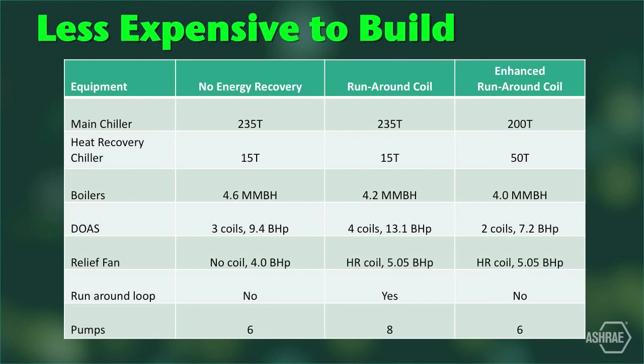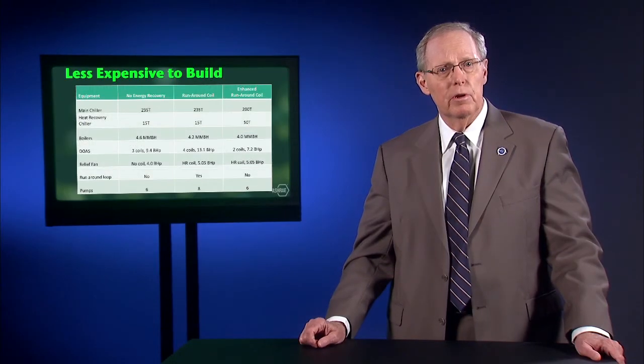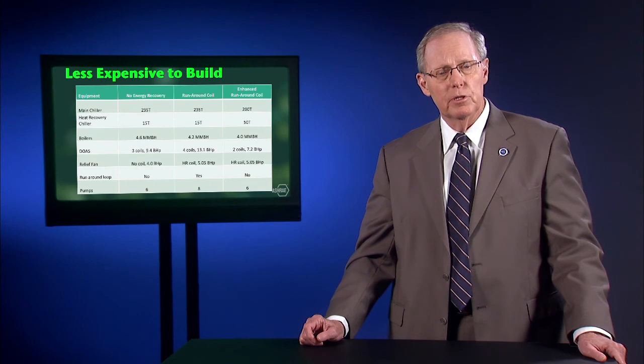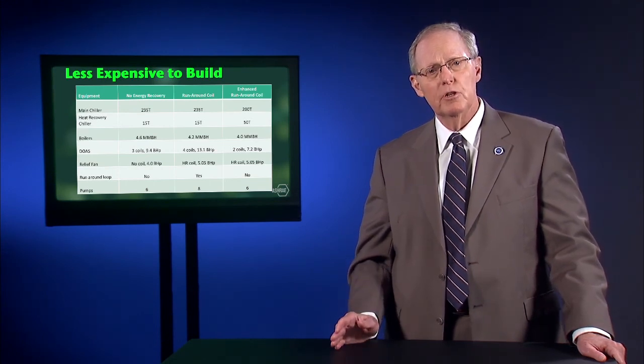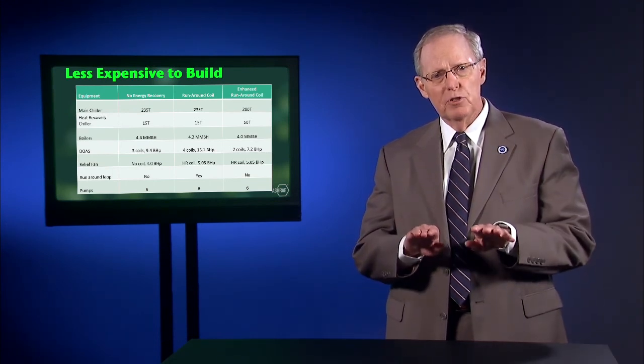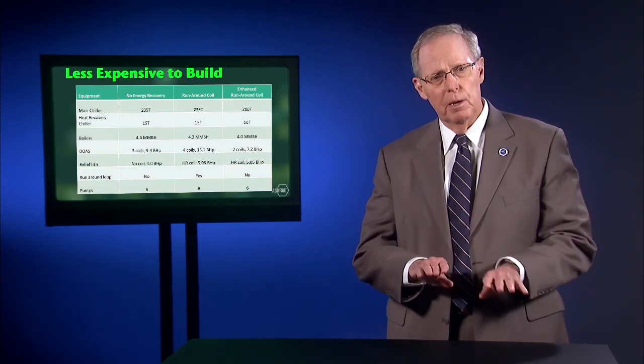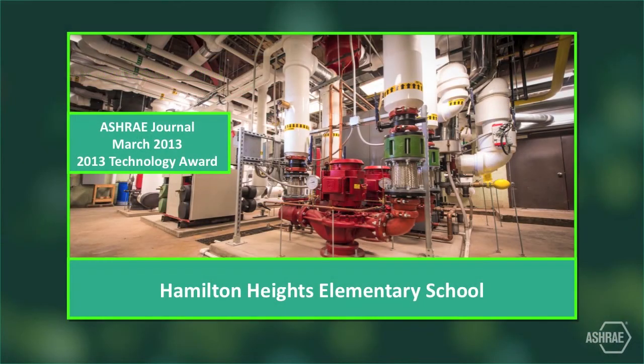And unlike most of the heat recovery solutions listed in Chapter 26, this one does not need the makeup and the relief air paths to be next to each other. One could be in the basement and the other on the roof, but as long as they're close to hot water and chill water mains, the energy savings will be available. Another advantage versus other air-to-air options, this concept saves energy even when the makeup and the exhaust air streams are at the same temperature. And not only does it work well, I mean, that's a good-looking mechanical room.